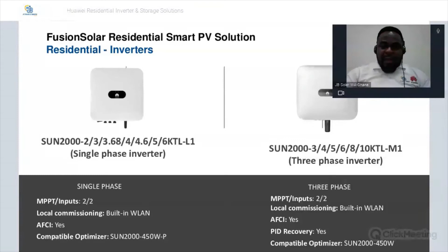If you are connecting batteries to this system, you can synchronize a maximum of 3 of these inverters. And in the synchro, you can mix and match. You can synchronize a single phase inverter with a 3-phase inverter, no problem at all. So you can put the 3 KTL L1 together with the 5 KTL M1, no problem. You can mix and match the synchro. But if they have batteries, you can do a maximum of 3. If they don't have batteries, you can do a maximum of 10. That is a very useful piece of information that we should all know at this stage.